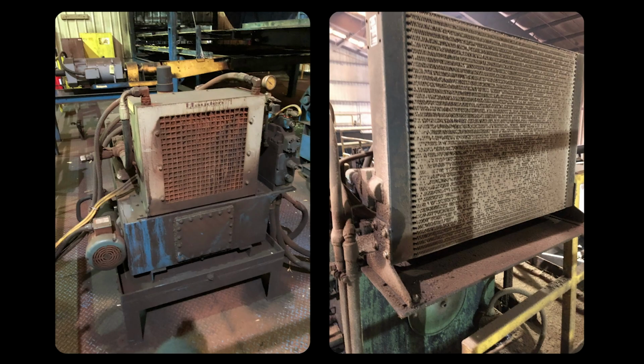More simple things that you can find. Here's two hydraulic units, and you can see the coolers or heat exchangers are actually fouled. So in both cases, these are shutting down because of high temperature, and they've been running that for a long time. And what we notice, of course, is we're damaging the valve, and we increase the wear in the pumps because the oil viscosity goes down. We're damaging O-rings and gaskets because of the heat load that they get. So these are things that are going to decrease the life of your equipment.